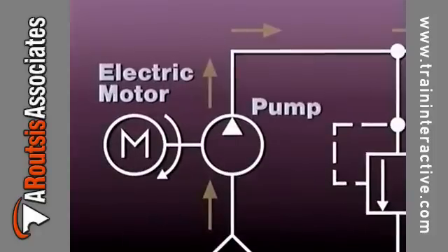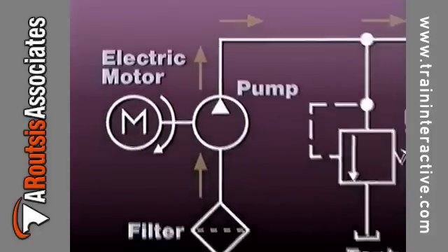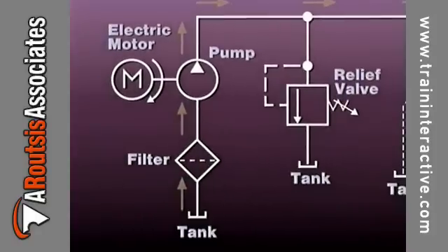As the electric motor turns the hydraulic pump, fluid from the tank is drawn through the filter and into the line. The pump's only function is to create flow. Pressure in the hydraulic system is created by resistance to flow.